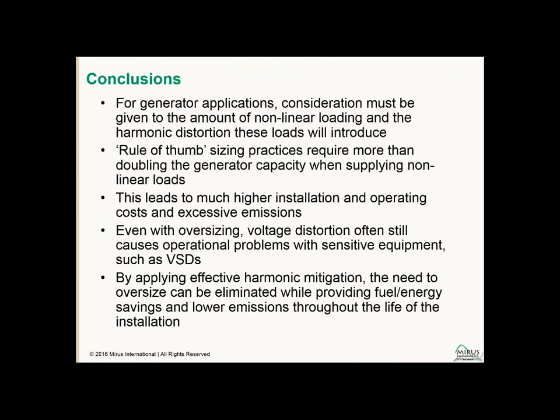So to wrap up then, if we look at generator applications, consideration must be given to the amount of nonlinear loading, and the harmonic distortion that these loadings will introduce. Rule of thumb sizing from generator manufacturers is to at least double, 2 to 2.5 times the generator capacity supplying the load. This leads to much higher installation and operating costs and excessive emissions.